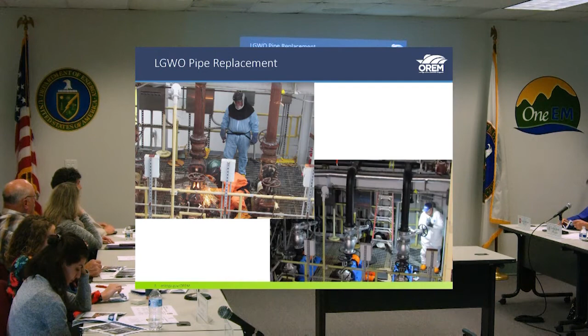This piping and valve system was one of the major headers between, I think, one of the clarifiers in the back, or at least one of the influent tanks. These pipes had a leak or something that caused them to remove the heat tracing or heat jackets, insulation jackets on the outside, and we found severe corrosion in these.